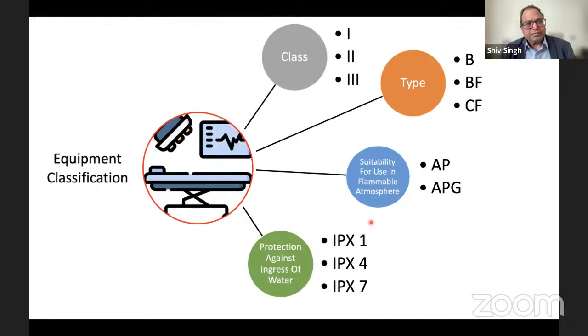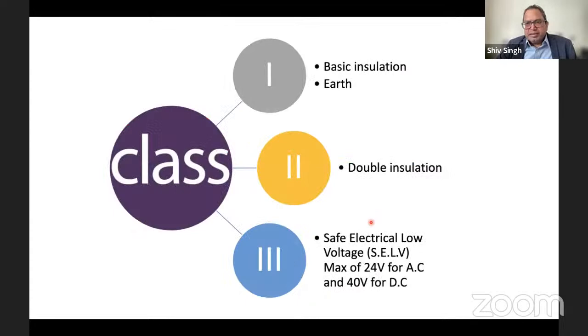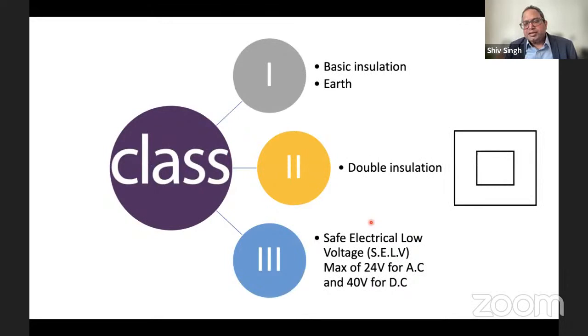So what is class 1 equipment? Class 1 equipment is basic equipment, like the ones we use at home. This one has a protective earth. That means the body of the equipment is earthed and connected to the earth in the socket. Now, class 2 is the only equipment which has a symbol, a box inside a box. So there's a basic insulation, and then another secondary insulation outside, so that the current cannot flow to the body of the equipment.